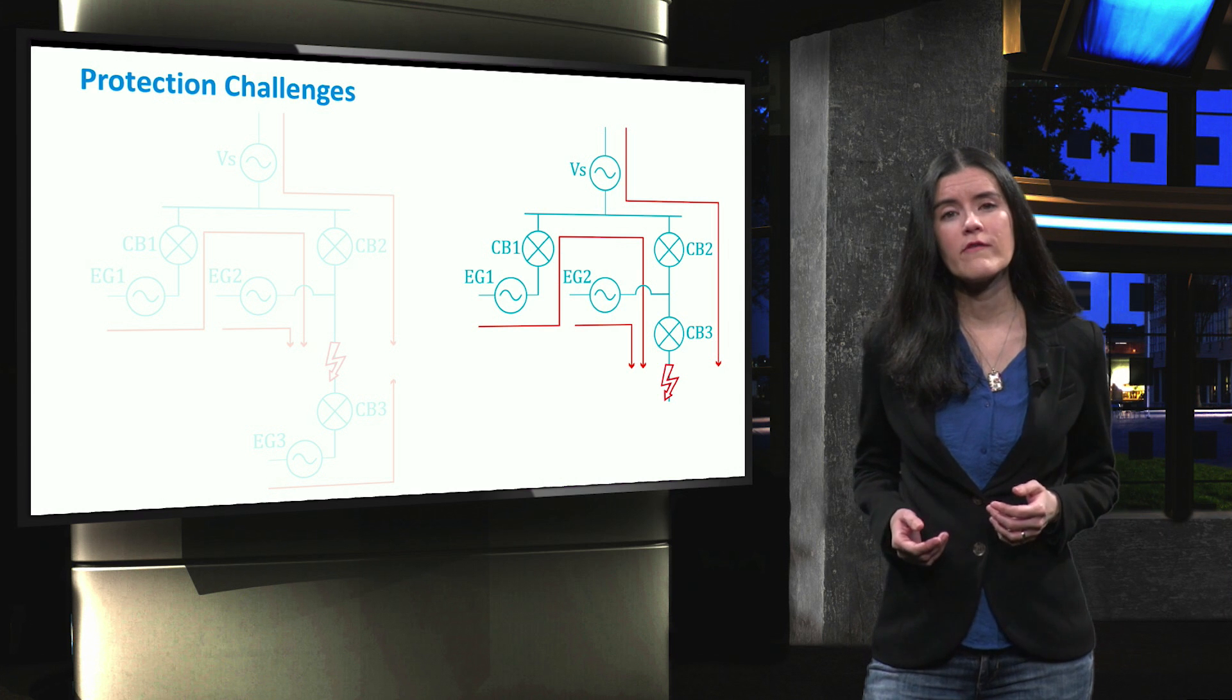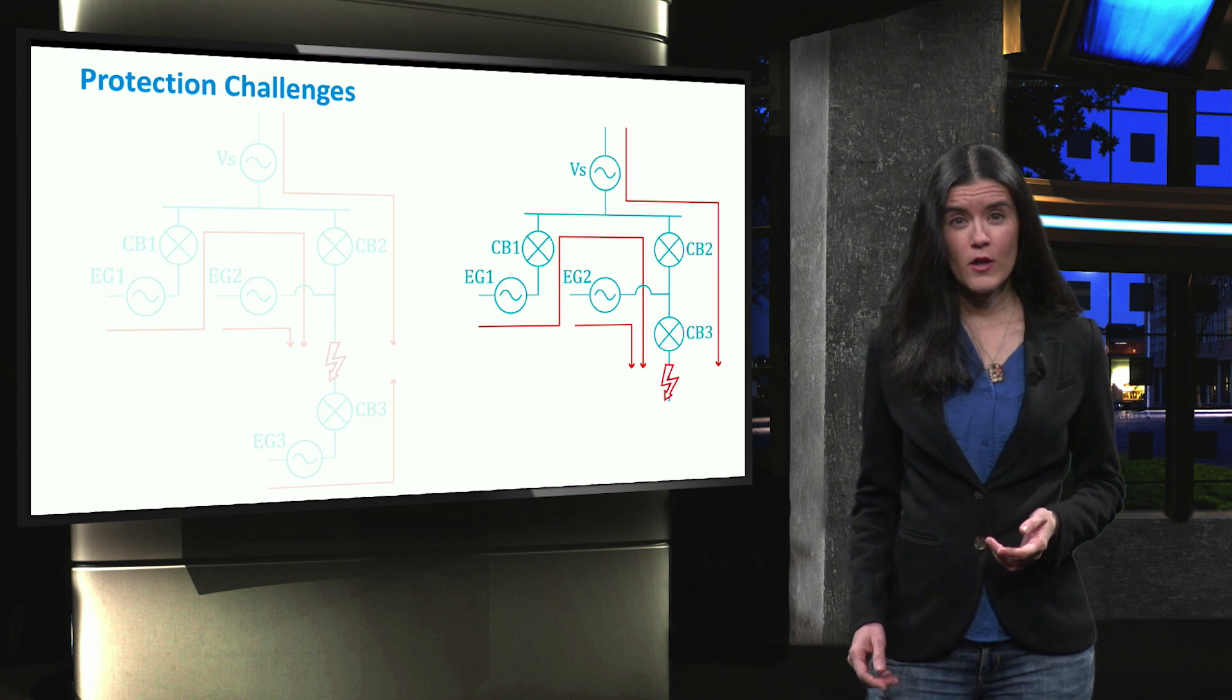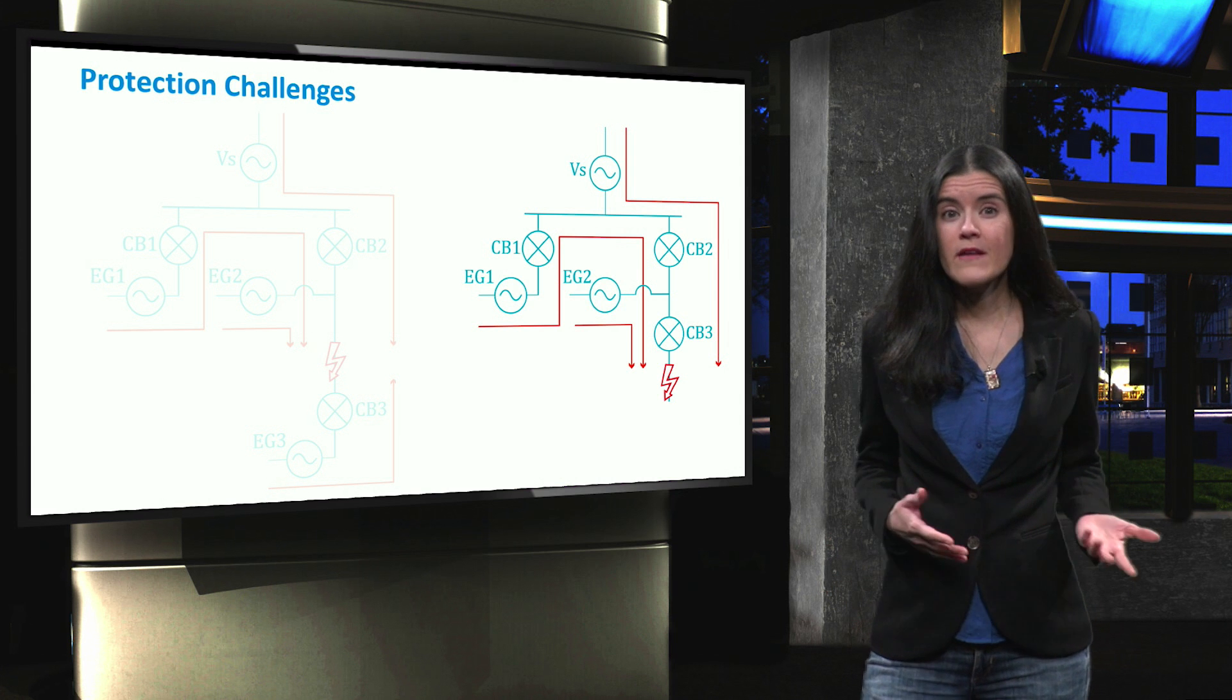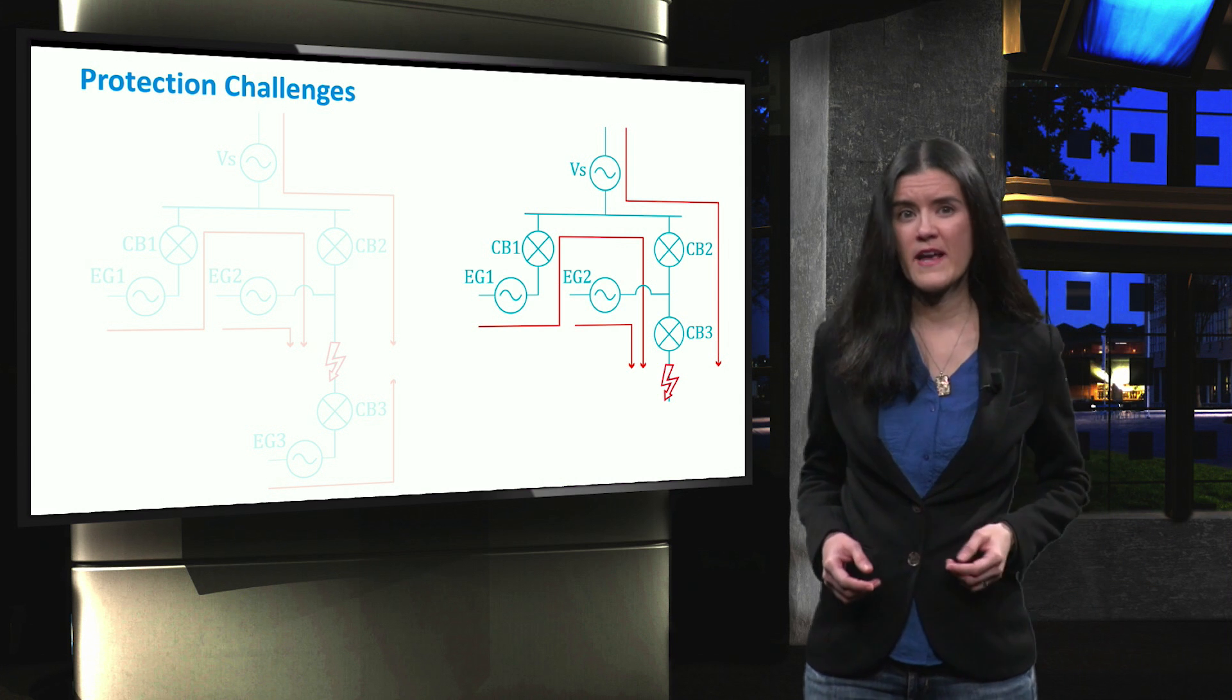In islanded operation, however, the distributed generators alone will contribute to the fault current, which can be much lower, making fault detection in that mode a harder task.